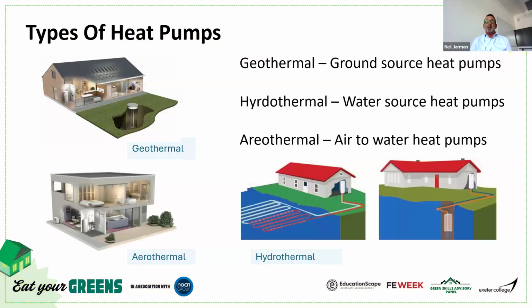So right now, the types of heat pumps: we've got geothermal, ground source heat pumps, hydrothermal, water source, and aerothermal, which I'm going to concentrate on. Just very quickly on the geothermal and the hydrothermal heat pumps, both of those are a little bit more efficient than an air source heat pump, purely because they both take a stable temperature. In the case of geothermal, the temperature is stable under the ground, and the same with a water source, if it's a lake or boreholes. You'll get a more stable temperature from those sources. Obviously, air to water is affected more by the outside air temperature. So with regards to air to water, the COP, which I'll go into in a little more detail, is slightly lower than what you'll get from a geothermal or a hydrothermal unit.